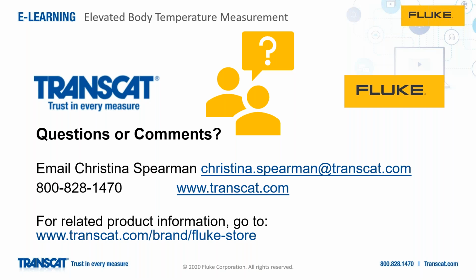So what we and our customers have tried to do is allow for as much time as possible or practical prior to coming inside, to let skin temperature acclimate. If there are erroneous readings, it helps to have an area for individuals to acclimate a bit more and screen again. There's no magic number, but the FDA recommendation is about 20 to 30 minutes to acclimate to the same temperature.